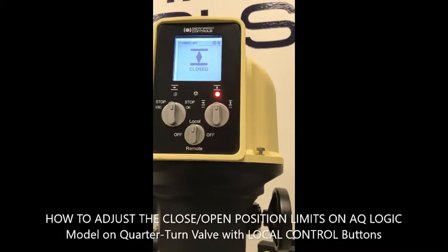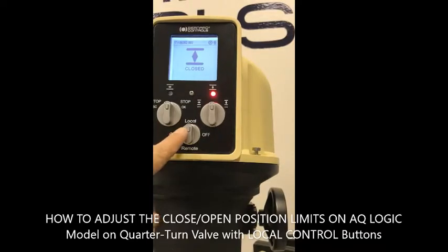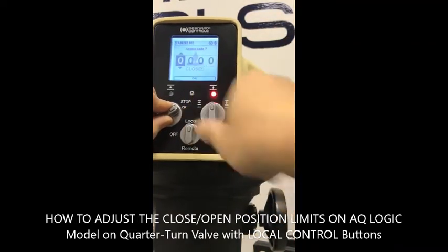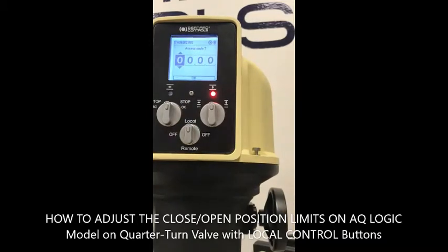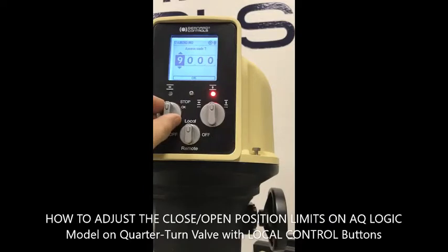Today you are going to set the limit position for close and open position for a quarter-turn valve on the AQ Logic model. First, you need to be in local mode — hold the stop button and go left and right with the right button. Enter the password 9000 to do the modification, then confirm.